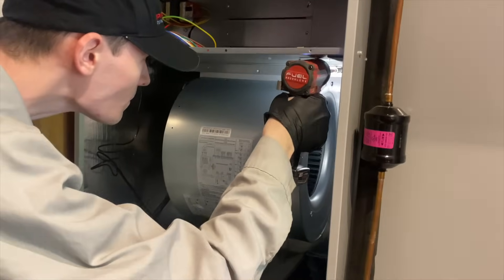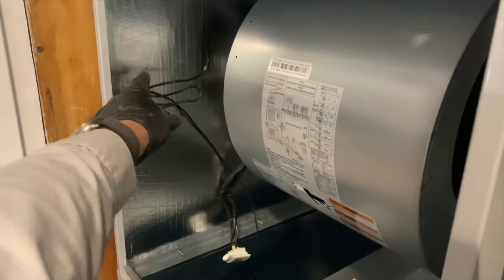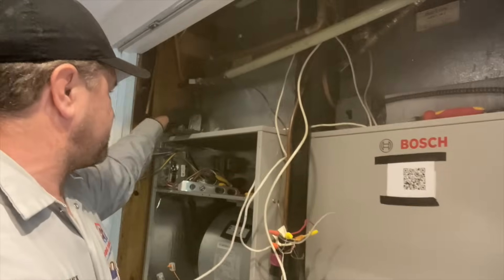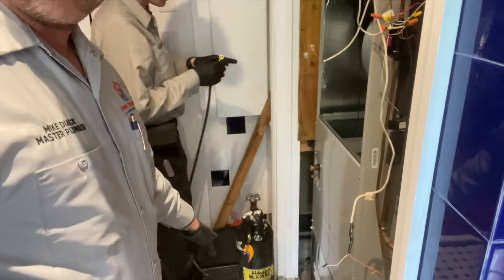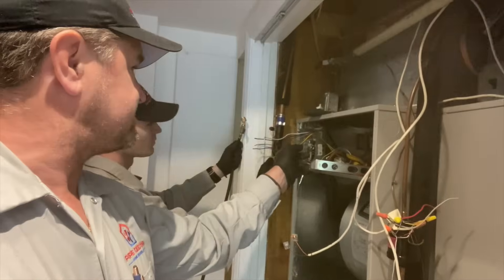We took out the blower motor. This wire here is the thermistor — the coil thermistor. I've been working on the electrical, the line voltage, and the low voltage. Daniel has a tank of nitrogen here.